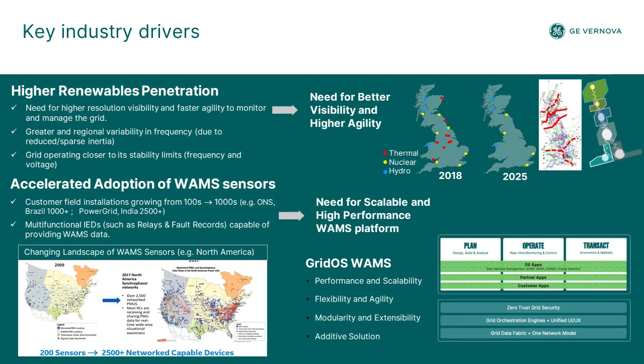The other trend that I'm seeing is the acceleration of these sensors. So 5 or 10 years ago, we had dedicated devices called Phasor Measurement Units that needed to be installed, and installing these devices was costly. What's changed is existing relays or fault recorders have the ability to gather this data, WAMS data. And so that's resulted in an explosion of these sensors across the grid. For example, if you look at North America, in a short span of 10 years, the number of devices across North America has grown from a few hundred sensors to thousands of sensors. And therefore, there is a need to be able to scale and consume these large volumes of data.